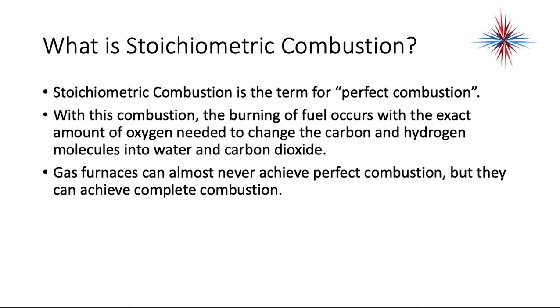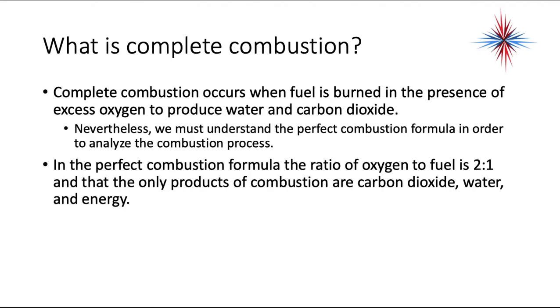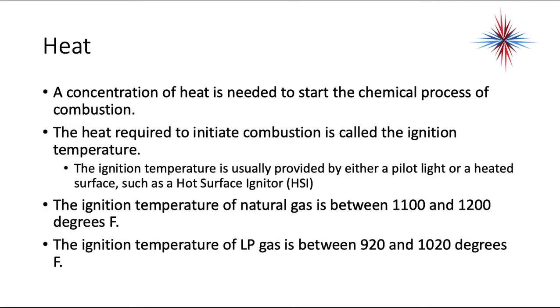Gas furnaces can almost never achieve perfect combustion, but they can achieve something we call complete combustion. Complete combustion occurs when the fuel is burned in the presence of excess oxygen to produce water and carbon dioxide. We must understand the perfect combustion formula to analyze the combustion process. In that formula, the ratio of oxygen to fuel is 2 to 1, and the only products are carbon dioxide, water, and energy.